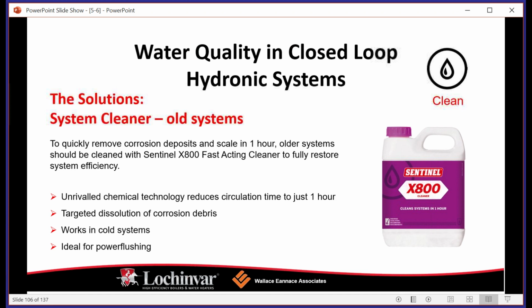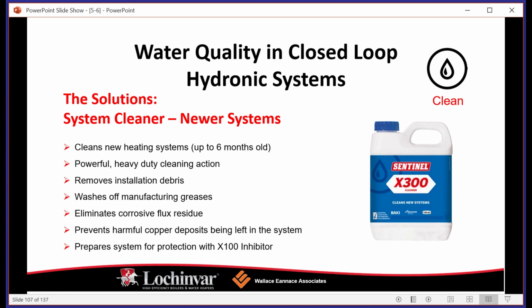So again, oxygen ingress, dissimilar metals in direct contact, right? Using dielectric unions, if you are using old cast iron pipe and your new boiler is using a copper header, you want to 100% make sure that you drop the cash and use those dielectric unions, because they will create an issue over time. And sludge fouling, oxygen ingress, these all could be pre-existing in boiler jobs you're going in to do. On new construction, you've got a new house, you're putting in a McMansion, you've got an FTXL or a Knight XL, something like that going in, you're probably going to be fine. You're going to refill with clean water, you can put a treatment in, and you shouldn't have any issues.